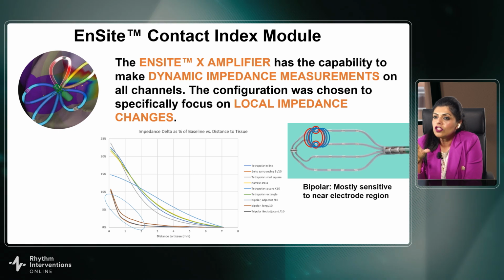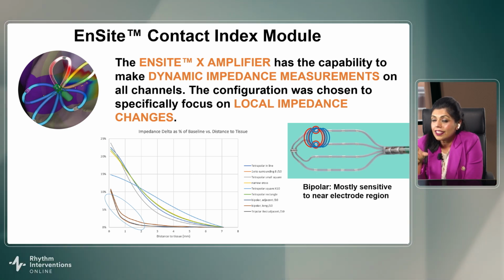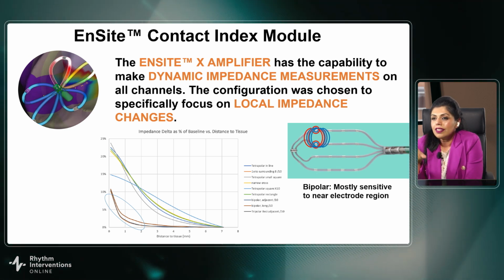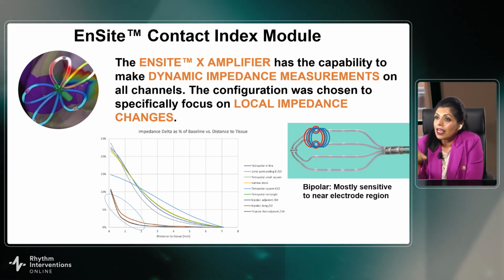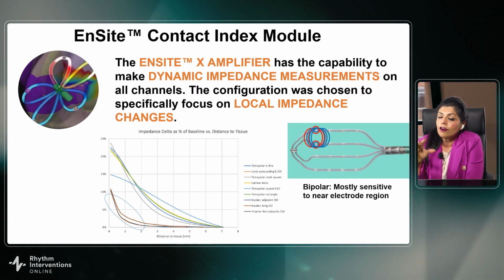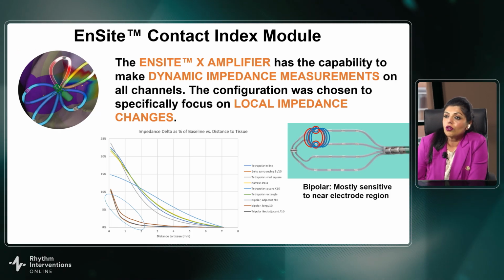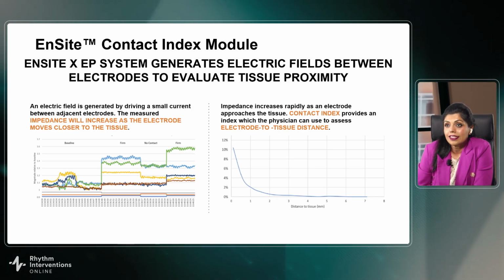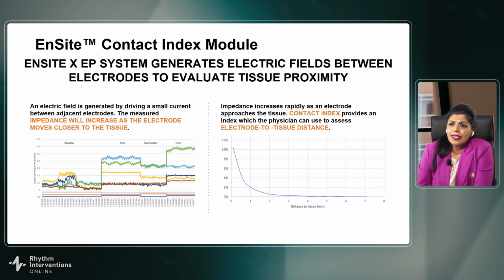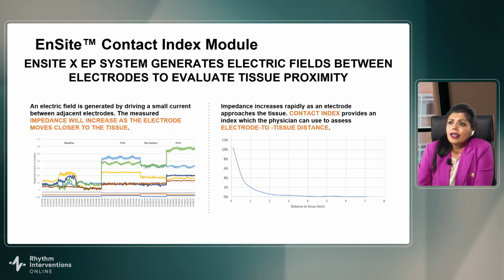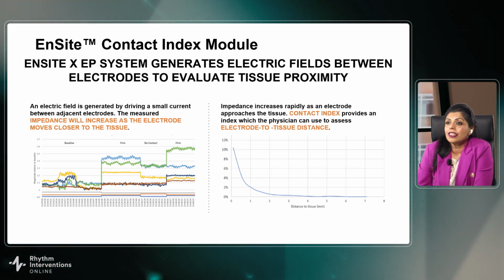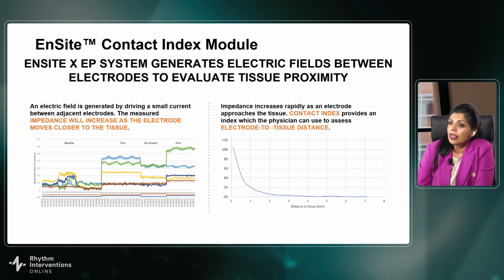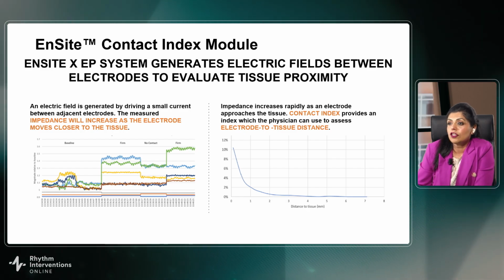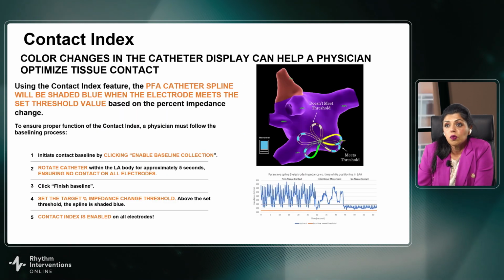Now, the other feature that I'll showcase is the contact index module. This is a module within the NavX system that allows for dynamic impedance measurements. So you can, for example, with the pentaspline catheter, look at the local impedance changes on the local splines and get an idea of the contact assessment. And the NavX system has historically used impedance-based tracking and change in impedance to track contact, and this is something that's been leveraged onto the PFA platforms as well.